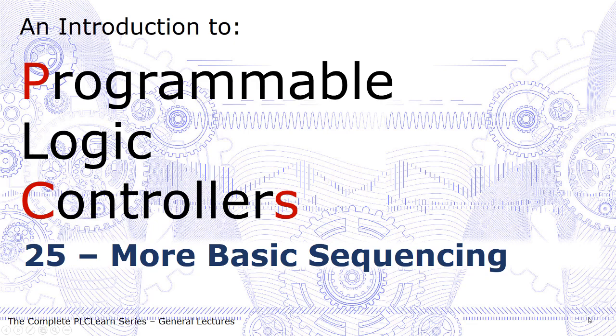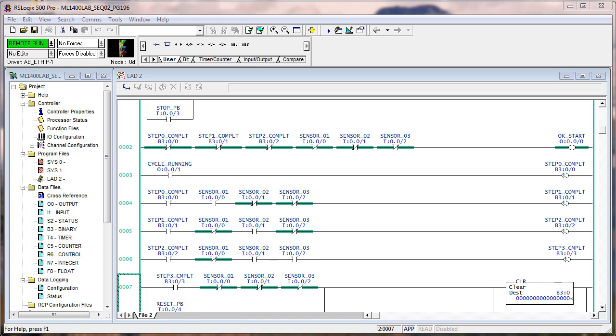More basic sequencing. This is where we left it at the tail end of the previous lab, and we're actually continuing with the same sequence of events, but we're going to move into seal-in logic and away from latch-unlatch. And as I said before, if you use latches, as we say in the business, you have to unlatch the whole world. If you just go through writing code, latching everything, because you don't want to use more difficult to write logic, then when you get all done, you've got to go back and find all those things that you latched and figure out when and how to unlatch them, which makes for some very difficult to read code.